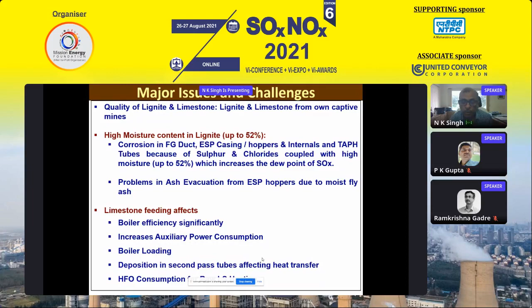Apart from this, lime feeding, which we do for sulfur capture, is causing a problem in boiler efficiency, and it increases the auxiliary consumption of the boiler. As well, for pulverization we need limestone mills, and their consumption is almost 34 to 35 kilowatt per ton. So that is additional auxiliary consumption. Then boiler loading is also badly affected, because lime deposition in the second pass tubing and superheater affects heat transfer. And then there is HFO consumption, because for limestone we need to give HFO for drying out and for proper pulverization.